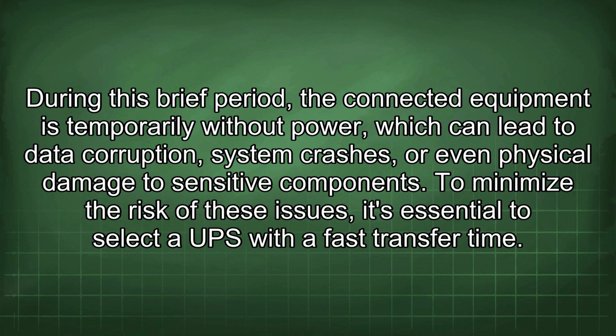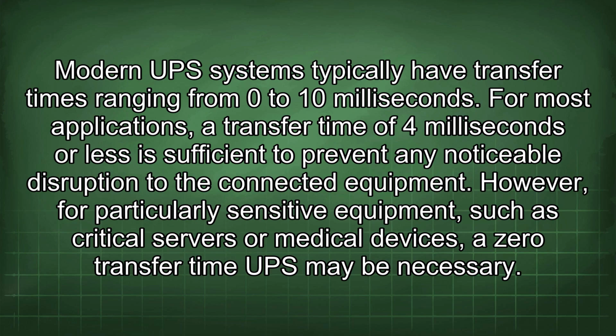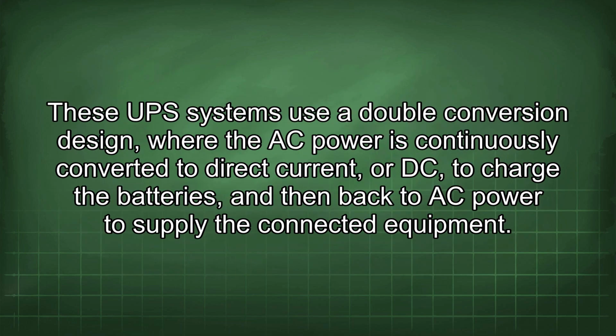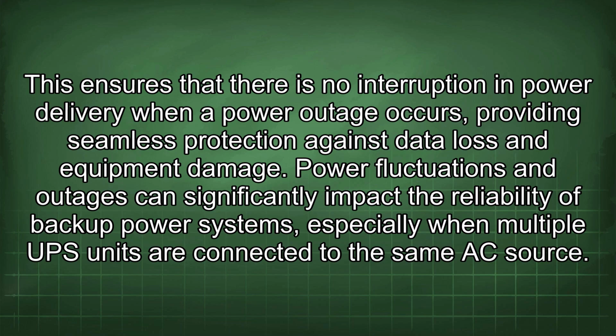To minimize the risk of these issues, it's essential to select a UPS with a fast transfer time. Modern UPS systems typically have transfer times ranging from 0 to 10 milliseconds. For most applications, a transfer time of 4 milliseconds or less is sufficient to prevent any noticeable disruption to the connected equipment. However, for particularly sensitive equipment, such as critical servers or medical devices, a zero transfer time UPS may be necessary. These UPS systems use a double conversion design, where the AC power is continuously converted to direct current, or DC, to charge the batteries, and then back to AC power to supply the connected equipment. This ensures that there is no interruption in power delivery when a power outage occurs, providing seamless protection against data loss and equipment damage.